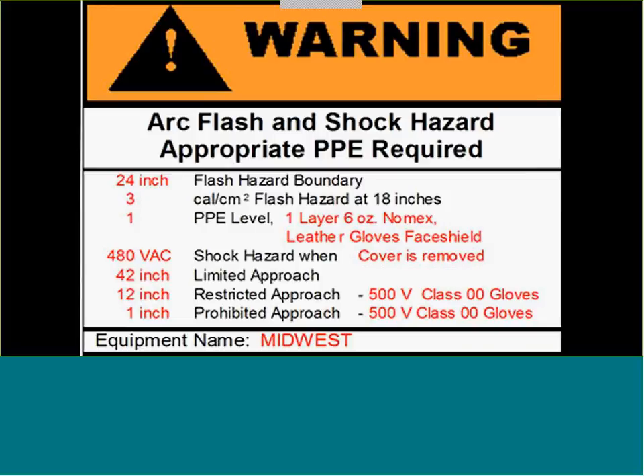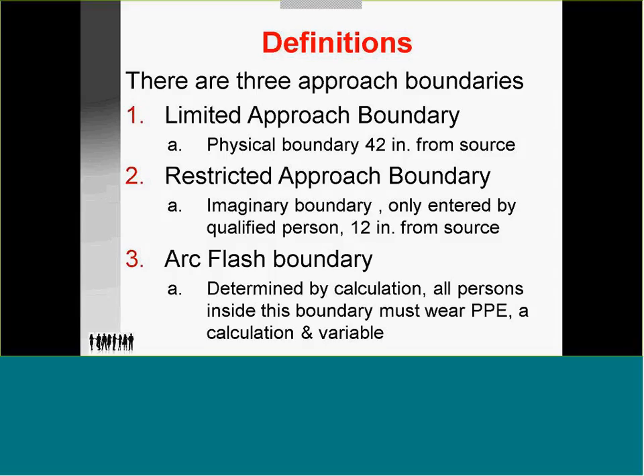Unqualified persons are not permitted. Now, this shows a prohibited approach. That has now been removed. It was 1 inch. You have all your gear on once you get within the arc flash boundary. So, remove that. There are still labels showing it, and it's no longer recognized. There are 3 approach boundaries. The limited approach is 42 inches. The restricted approach is 12 inches for most sources. The arc flash boundary is determined by calculation.